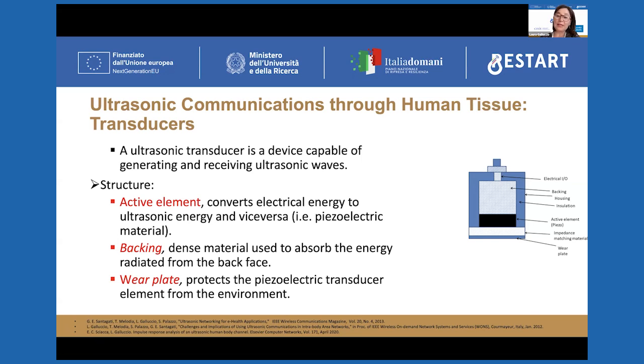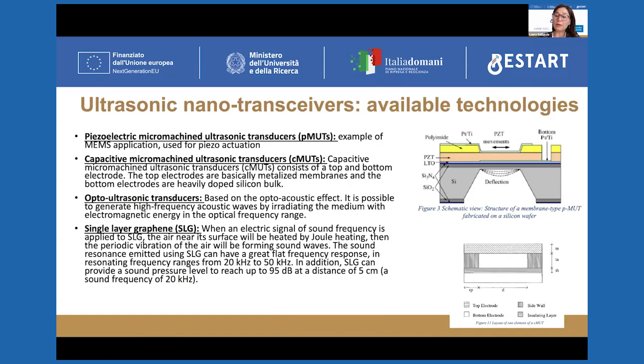For example, in case of a piezoelectric transducer like this one that I have reported here, we have always an active element, this one, for example, in case of a piezo. This is the black rectangle here. Then there is this backing, which is used to absorb the energy radiated on the back face. And then we have a wear plate that protects the transducer.